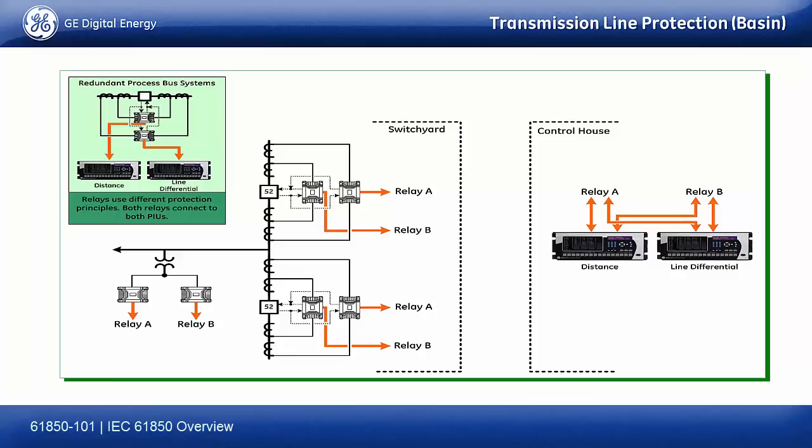And if I design my system right, as we've done in the UR and HardFiber, we can have redundant bricks that operate in a hot standby mode, and our relays can use the redundant bricks. So if one brick is out of service for some reason, the relay uses the data from the other brick. If I cross things like this, I have complete reliability of measurement and protection, right?